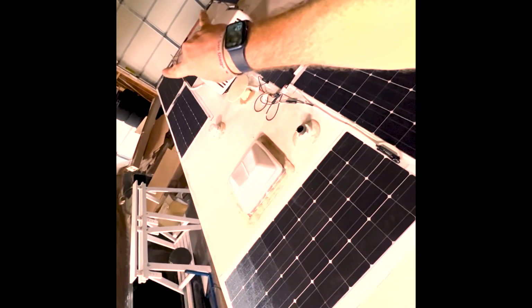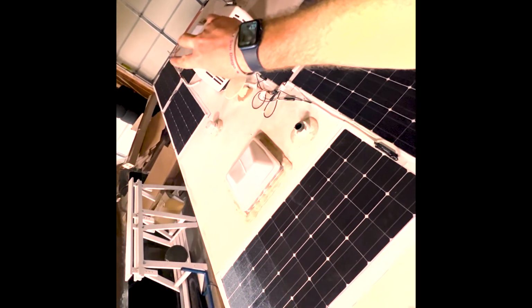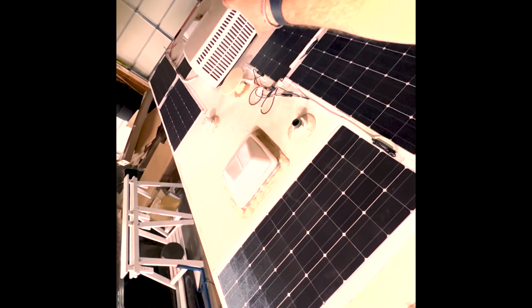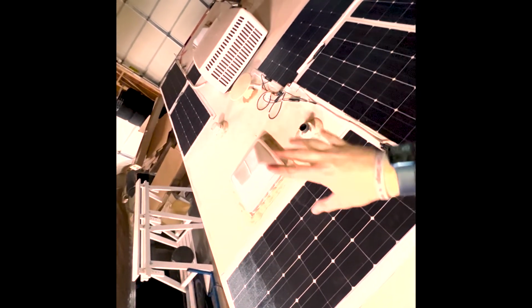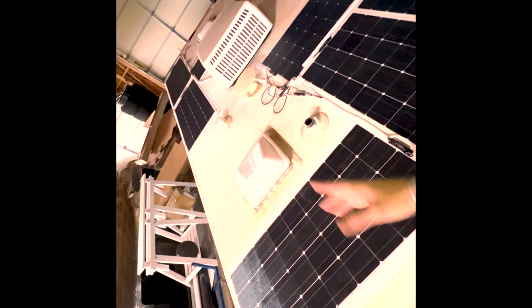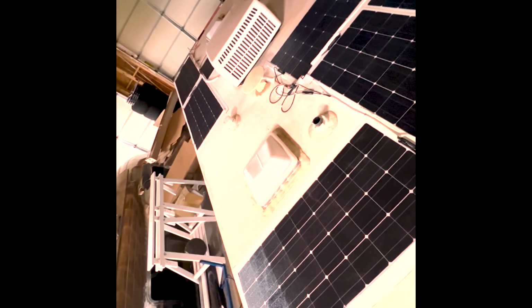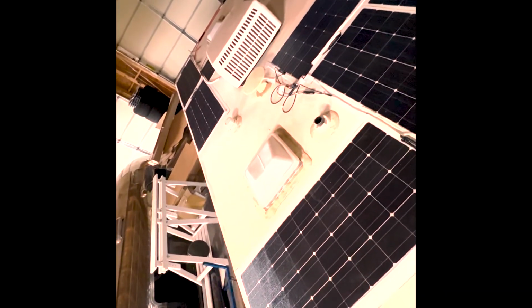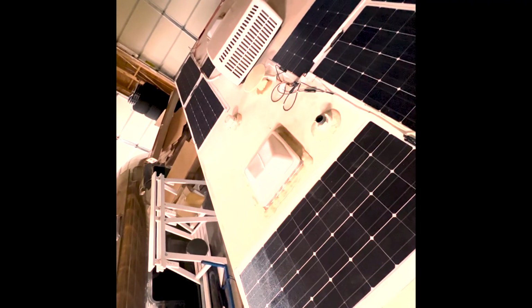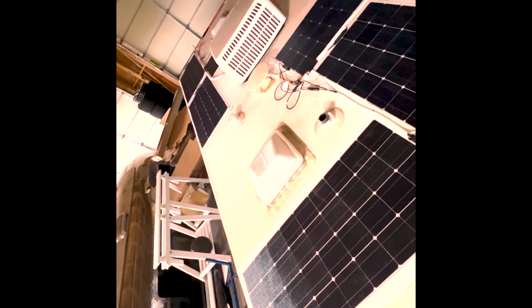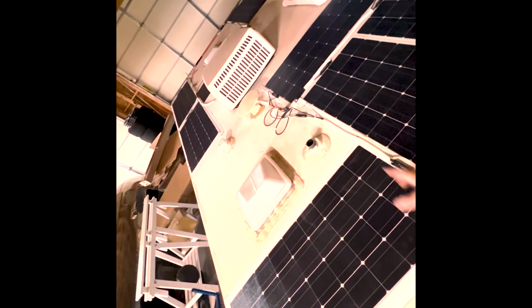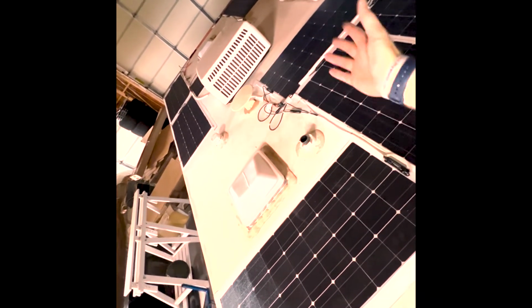Then they parallel in with this group of 4, which is also run in series. So you've got 2 sets of 4, bound together for one set of wires that runs down. It's easier to do it with one set of wires running down than to bring both sides and join it down there, because the wires can handle the current for something like this. They can handle like 15-20 amps, and this is never going to be more than half of that.